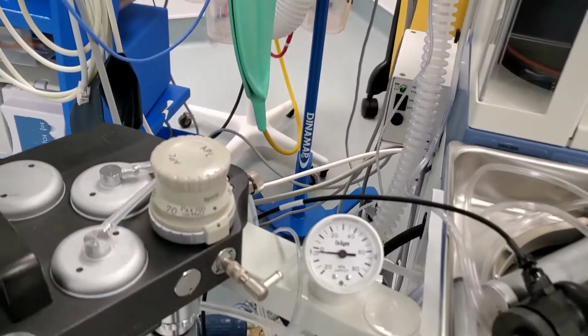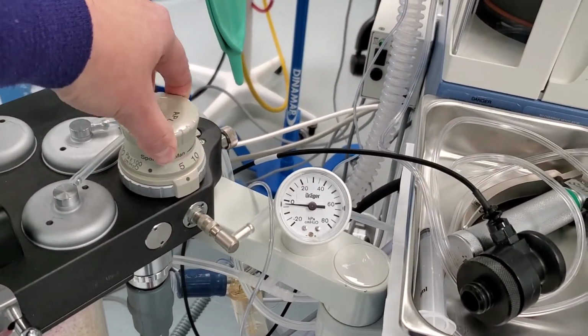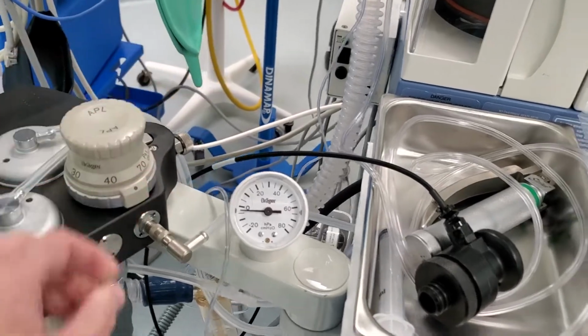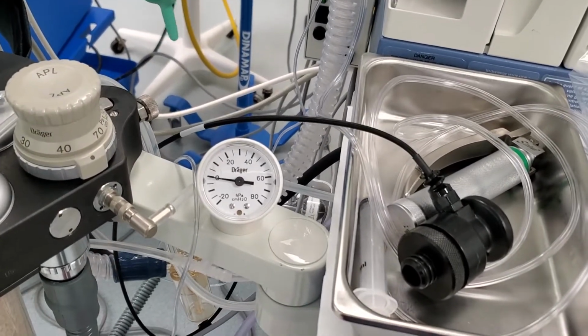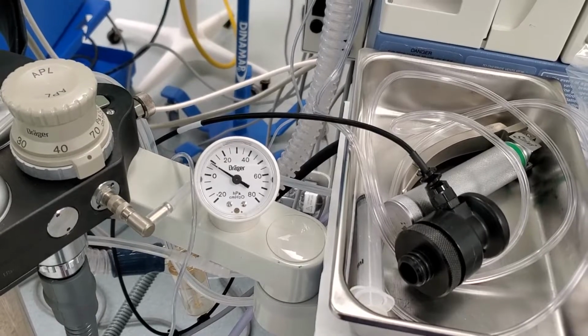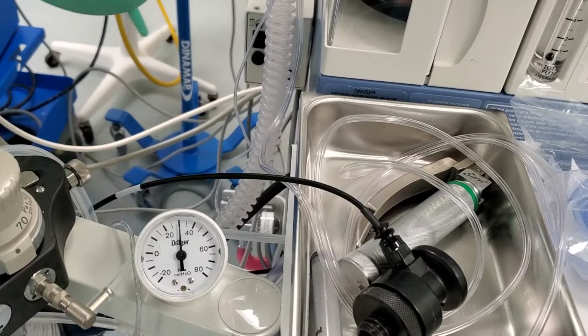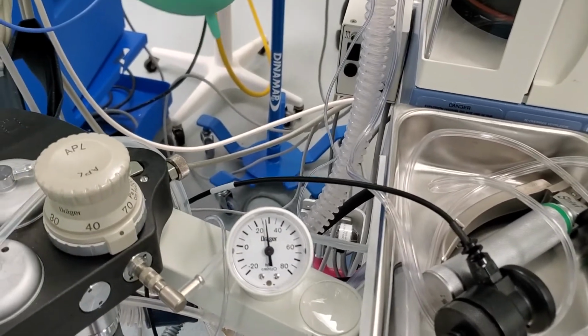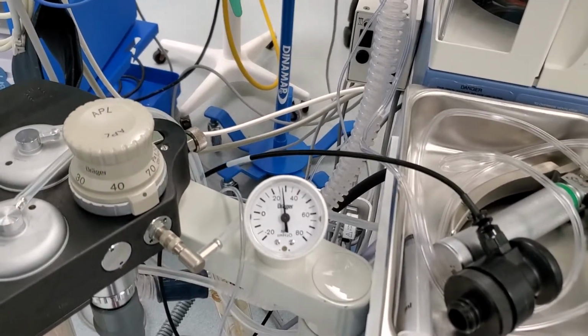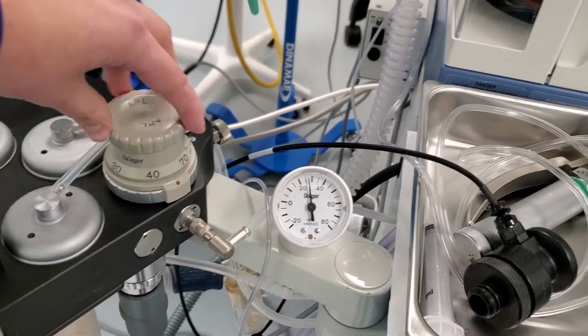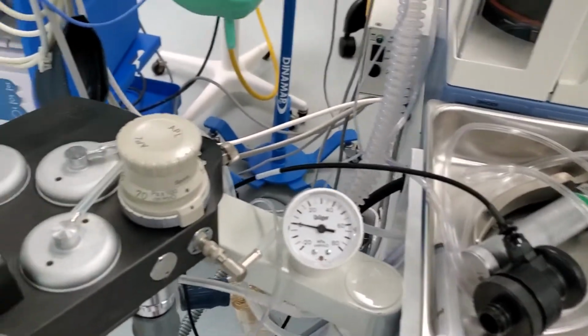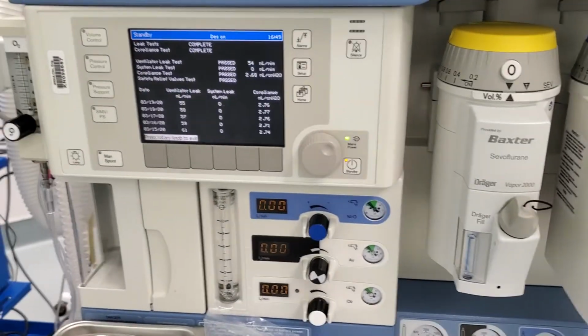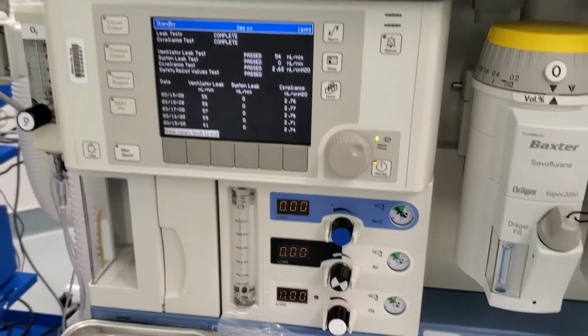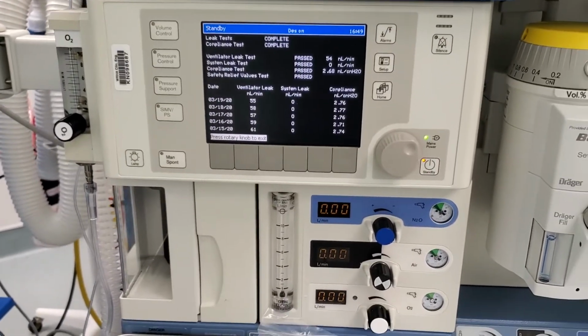I'm just going to simulate a simple leak test of what we do when we put on a new circuit. So we just close the APL valve again, push the O2 flush button to reach a pressure between 15 and 30. And then we just give the bag a couple squeezes just to generate a bit higher pressure to make sure that there's no leaks at higher pressures. As long as the needle doesn't drop, then you're good to go. So we release the pressure on the APL valve, and the machine is considered checked and ready to go. So we do that every morning. You'll be learning that as a student when you come here throughout your rotation.